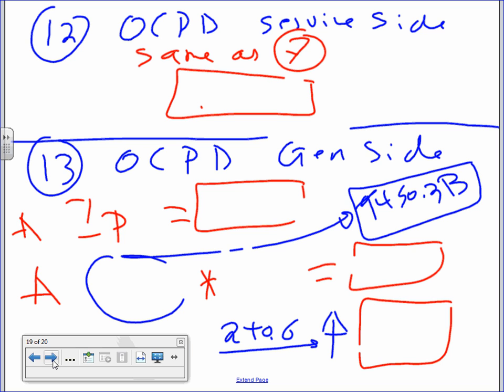Now, the overcurrent protection device on the service side is the same as number 7. So this is number 12, same as number 7, and we came up with 1000 amps. You guys remember the same calculation? The last thing is conductors on the generator side, my friends, which is going to be slightly different.